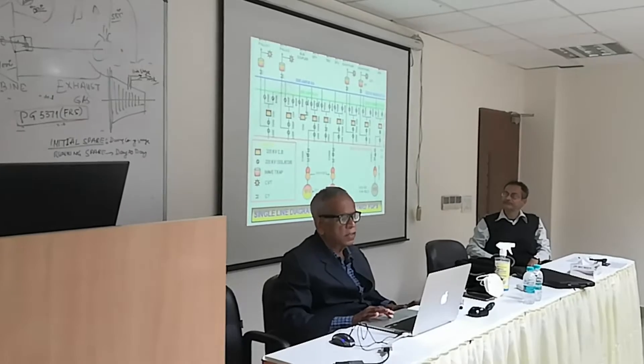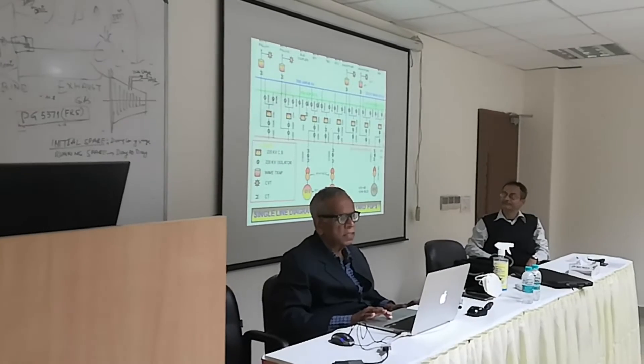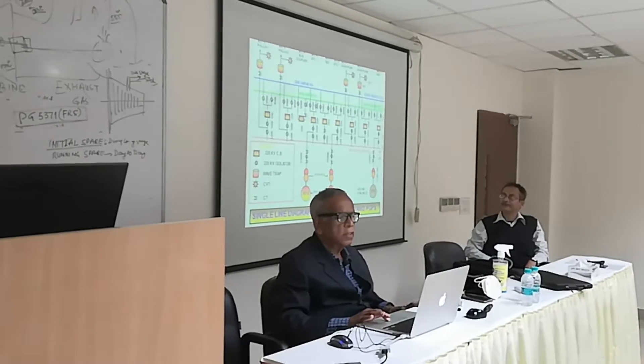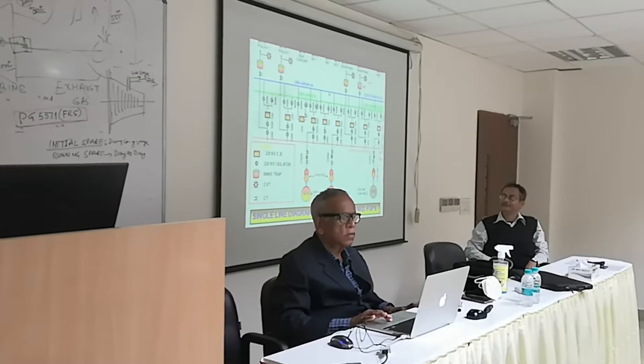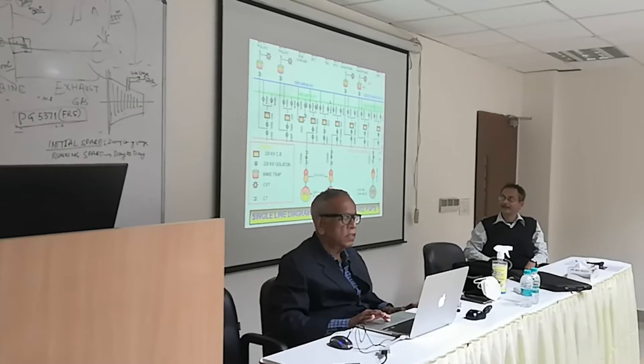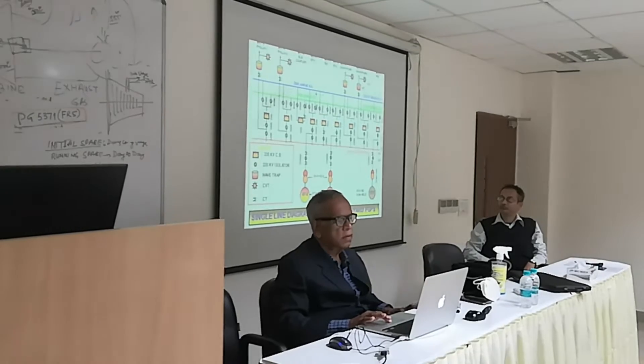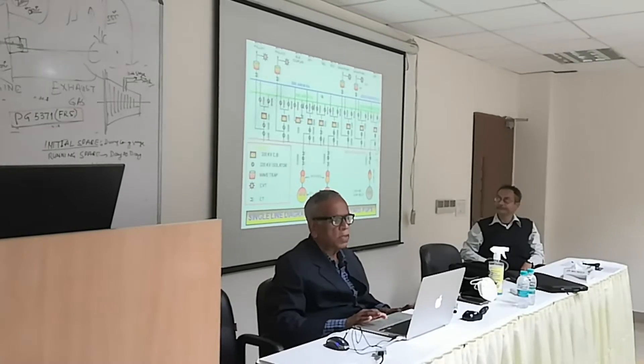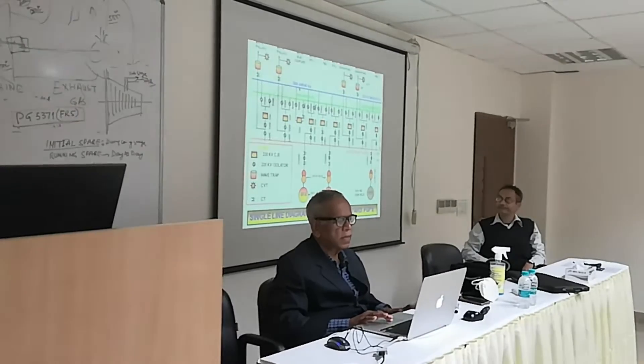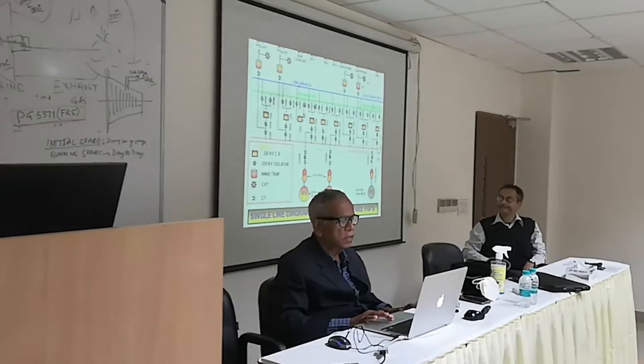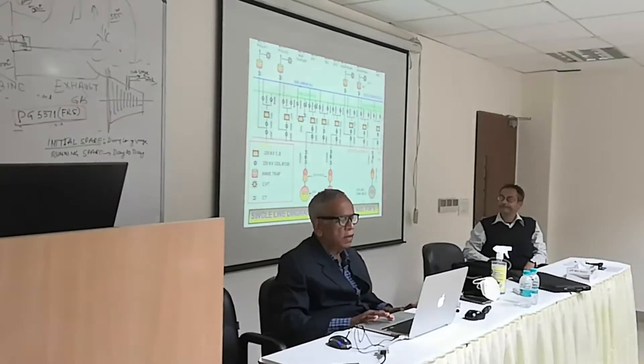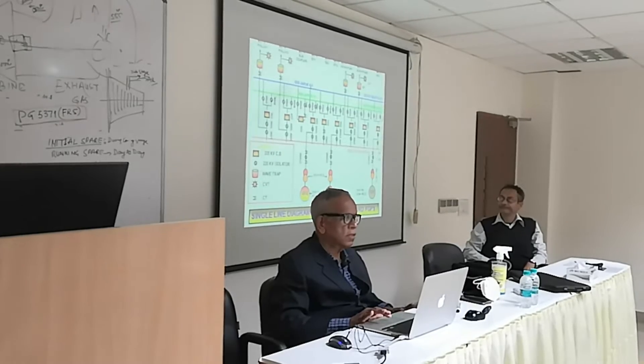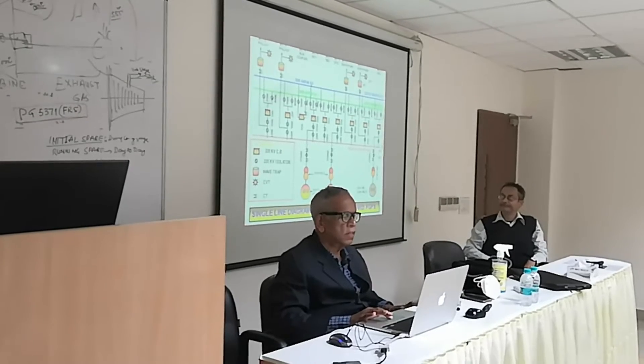This power is then injected into a switchyard which has got three 220 KV buses. Bus one has a rating of 2500 A and a short circuit rating of 40 KA.